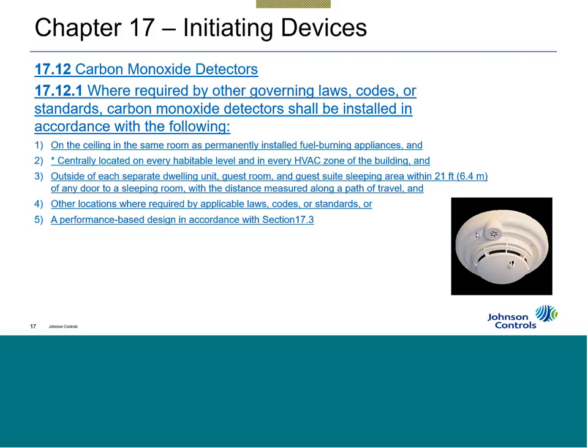So the committee realized that, and the committee said, we do not want people to overestimate where their carbon monoxide devices will go or overestimate where the smoke detectors go, because these are going to be combination devices. So why don't we take the one that's most stringent, smoke detectors, and say you need to have a carbon monoxide that's going to be tied to a smoke within 21 feet. So if you've done any spacing calculations with smoke detectors, 0.7 of the listed spacing to the furthest corner, the hypotenuse of the triangle, gets you to the 21 feet.